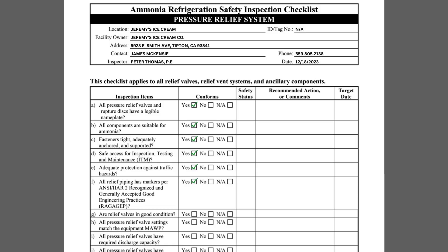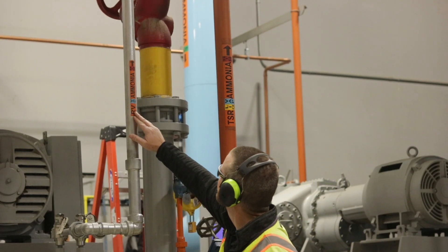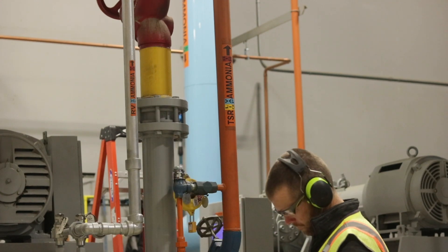Item F inquires if the relief valve discharge termination pipes are marked as required by IIAR Standard 2. Standard 2 requires piping mains, headers, and branches to be labeled. In the case of pressure relief piping, the pipe color should be gray. The physical state abbreviation should state VAP, which is an abbreviation for vapor. The relative pressure will be listed as high, and the service abbreviation should say RV, which stands for relief vent.